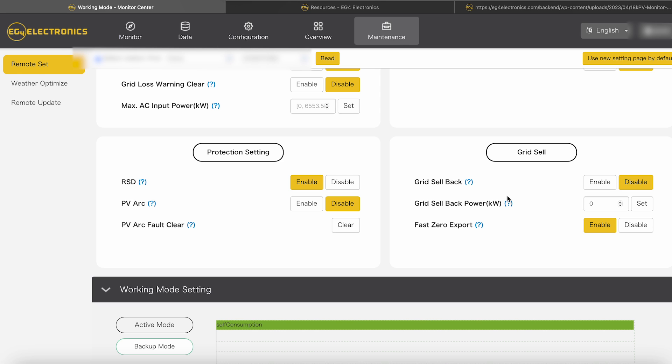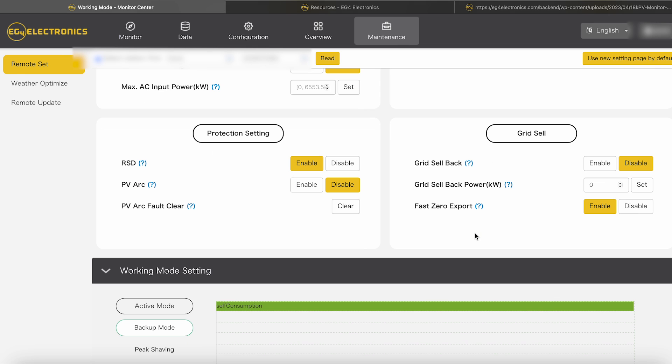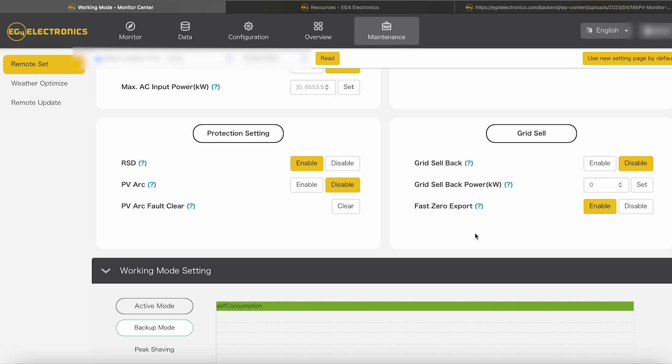So just make sure you have all that stuff set right before you actually have everything on. And then the fast zero export, you're going to want to have that enabled because if it's not enabled, you might accidentally sell back a little bit. So you want that thing to stop as fast as possible so it's not selling back to the grid inadvertently. And then also another thing is some people may be trying to put their CTs when they do their install right in your inverter itself, right at the connection for your inverter to grid input. But you're going to want to put that back in your main panel where your grid power is coming into your main house panel.